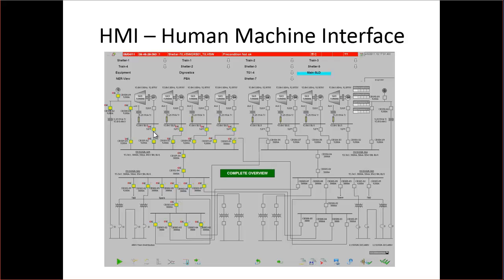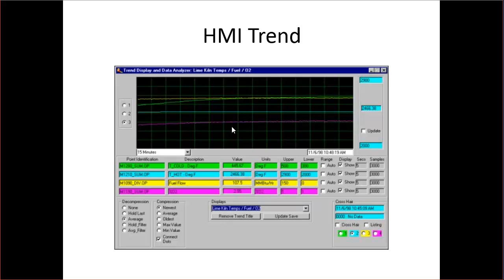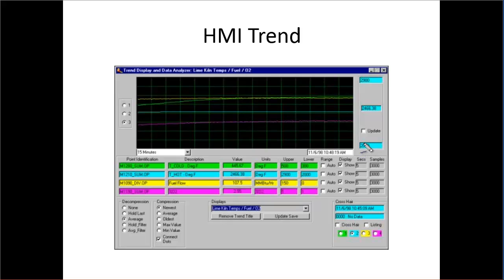We don't have any trends or gauges on this particular screen, but I do have an HMI trend here. This is just trends for a value over time — you can see it's bouncing around a little bit. The current time is shown here, and this shows you 15 minutes back, so this comprises a 15-minute trend. We can see the scale of the trend — the bottom would be 2000 and the top would be 2900.